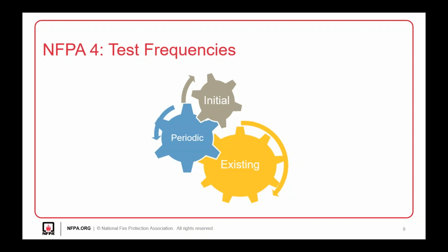When it comes to periodic testing, they decided it should be trigger-based. So when something is added to your integrated systems or revised, that's when an integrated system test should be conducted. I want to be clear the intent isn't to conduct end-to-end integrated system testing every time, like replacing a manual pull station or a horn and strobe. The idea is you'd take one of those devices on that zone and test it with the rest of your integrated systems. That's what we define as a control group test.